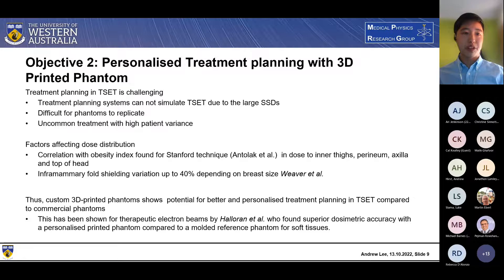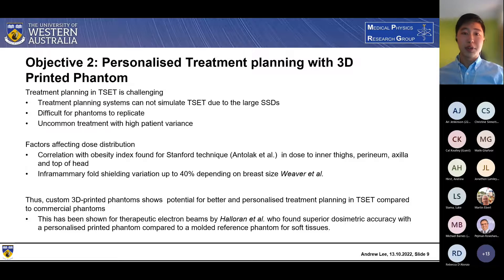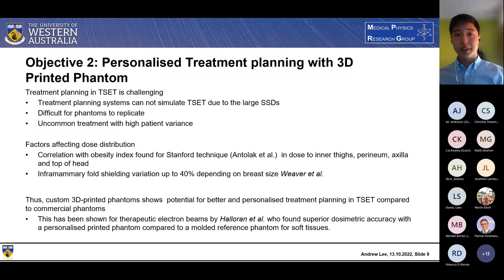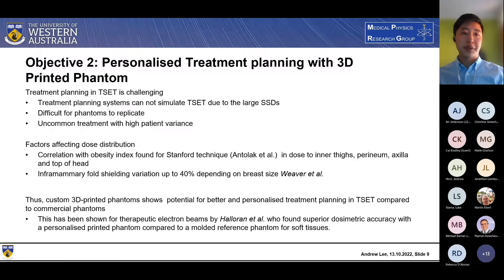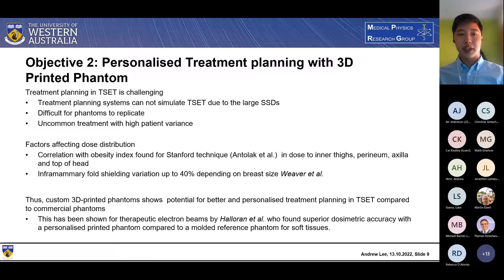This brings us to Objective 2: to solve that problem with 3D printed personalized phantoms. In total skin electron therapy, treatment planning has traditionally proved a challenge. Most therapies can be simulated with treatment planning systems, but this is not the case for total skin electron therapy, due to large SSDs ranging from around 3 to 7 meters, complex patient geometry, and the use of additional scattering plates to increase dose uniformity. There's also a correlation found for obesity index with the Stanford technique — expected to apply to the rotational technique as well — shown in dose to the inner thighs, perineum, axilla, and top of the head.